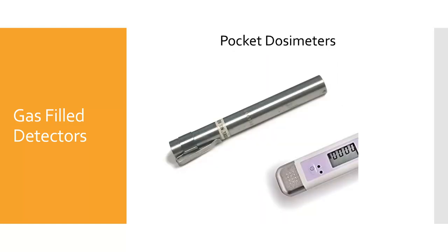The last gas-filled detector we will discuss is the pocket dosimeter, which is worn on the pocket to detect and measure the radiation dose the technologist is being exposed to in their duties. Pocket dosimeters are good for short-term monitoring because they are immediately readable, but they can be inaccurate if not properly used or if they are knocked around. We will discuss other more commonly utilized types of personal monitoring devices later in this video.